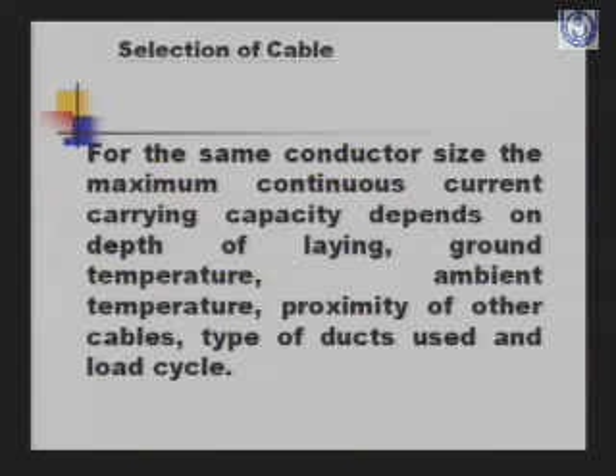For the same conductor size, the maximum continuous carrying capacity depends on depth of laying, ground temperature, ambient temperature, proximity of other cables, type of ducts used, and load cycle.